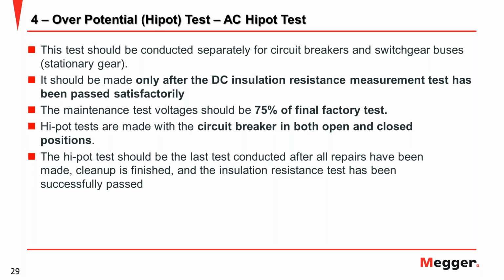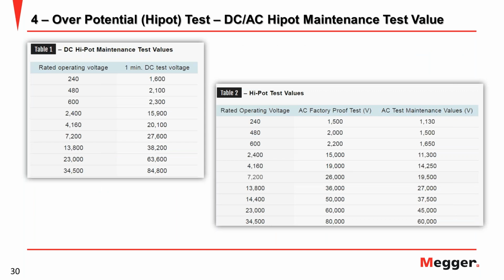The maintenance test voltage should be 75% of the final factory test. You need to do it in both open and close position. This is some information regarding the time duration and rated operating voltage if you use the DC or AC hipot. Some OEM breakers, as I know, are sometimes tested for more than 1 minute. They test for 15 minutes to see that the capability of the breaker is still okay at a certain voltage level.